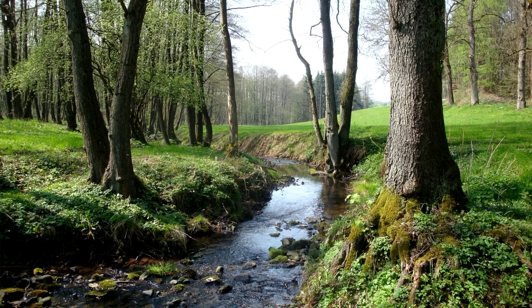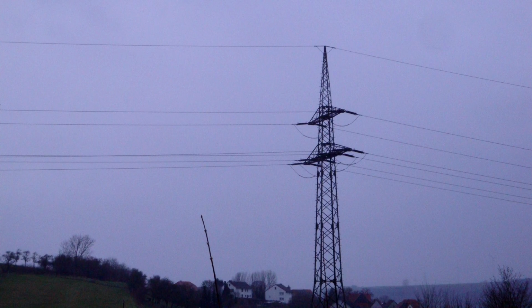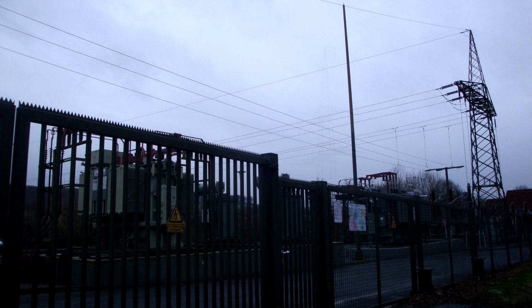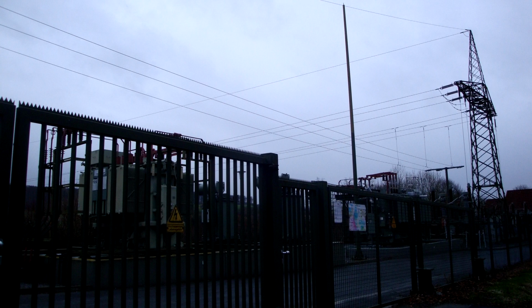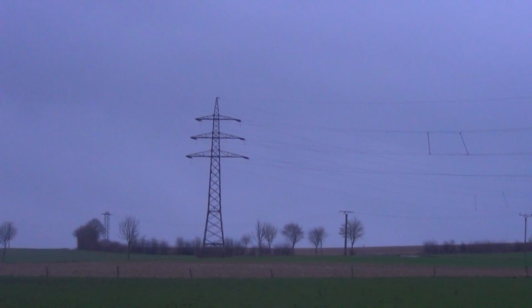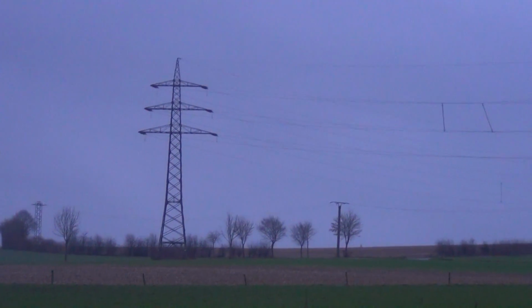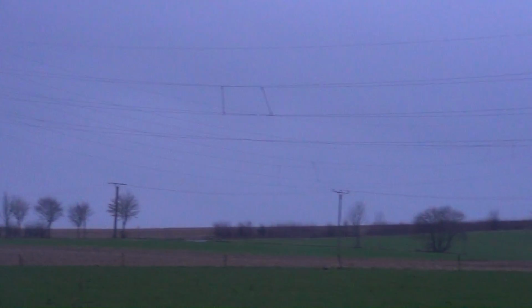I live in a rural area without any large-scale power plants. We have no extra high voltage transmission lines around here, but you often see 110 kV lines like the one on this picture. The 110 kV line is going to the local substation where the regional medium voltage grid is connected to it. Right here you can see both a high voltage and a medium voltage line next to each other.